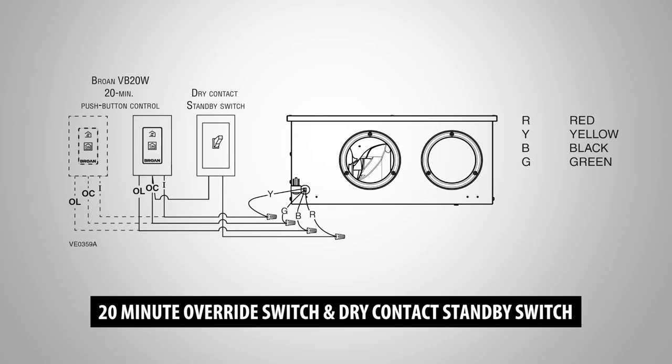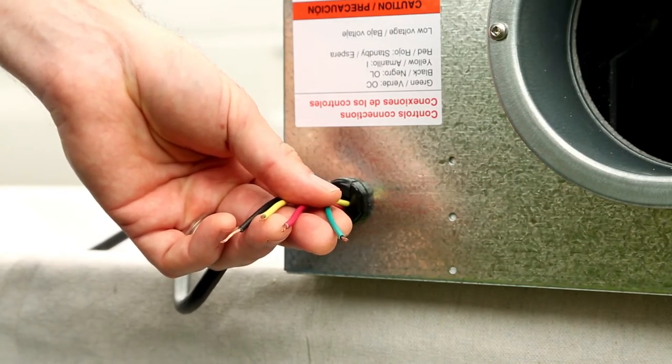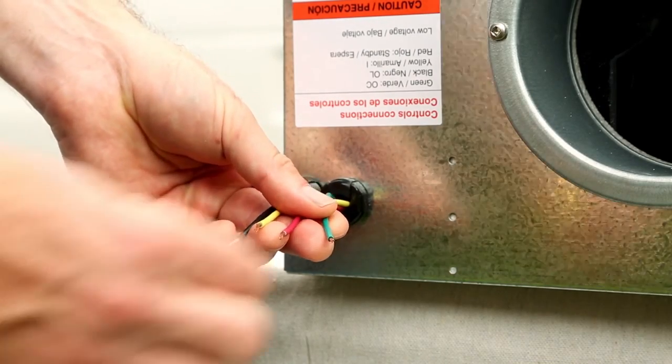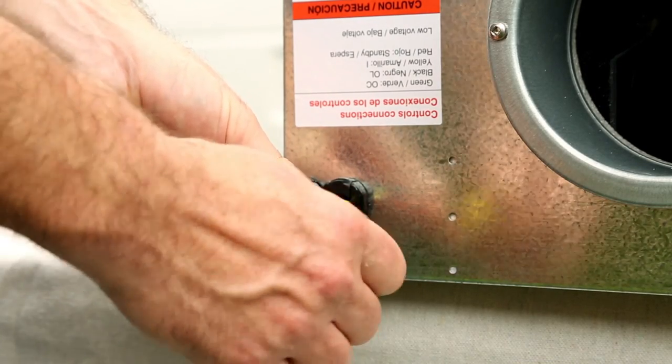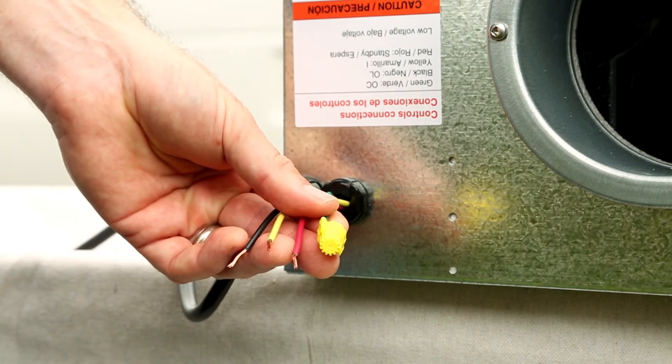Finally, the unit can be connected to a 20-minute override switch and a standby switch. This configuration allows for operation of the override switch even if the standby switch is turned on. The unit comes with red, yellow, black, and green wires. Regardless of the control configuration chosen, be sure to cap all unused wires.